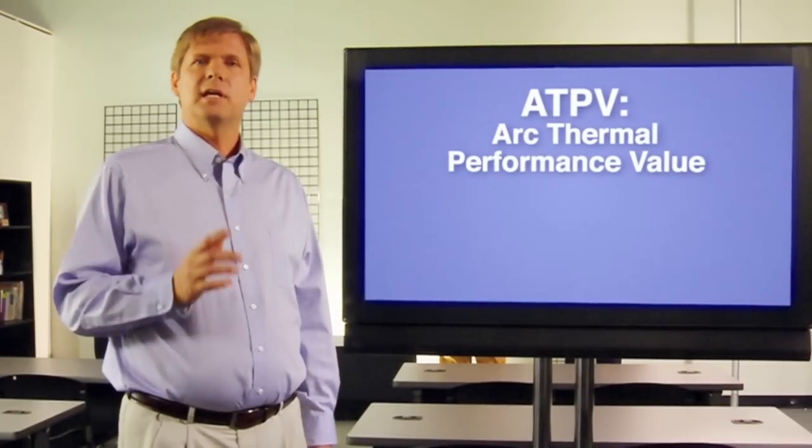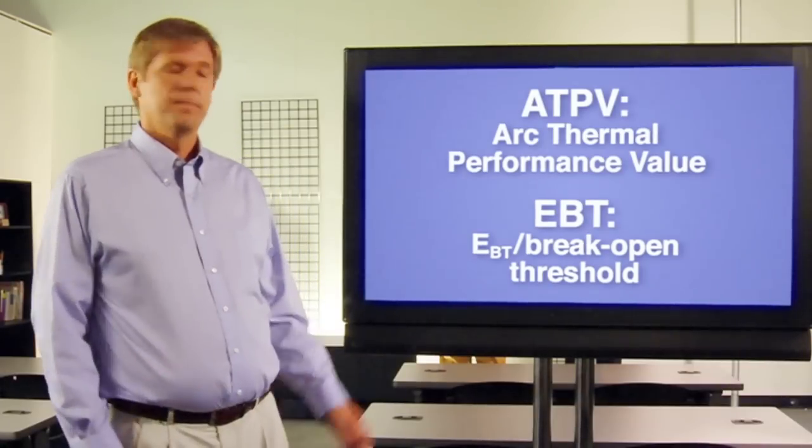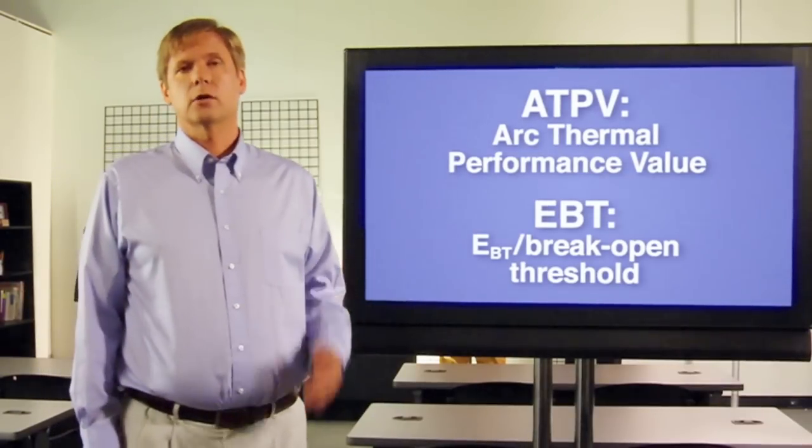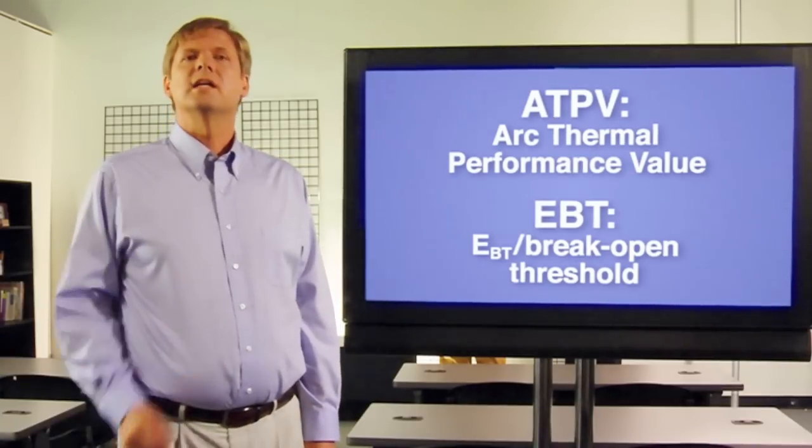As an ATPV or arc thermal performance value, or as an EBT or energy break open threshold. Both are arc ratings. Both are intended to measure the onset of a second degree burn. The more common arc rating value you will hear is the ATPV.